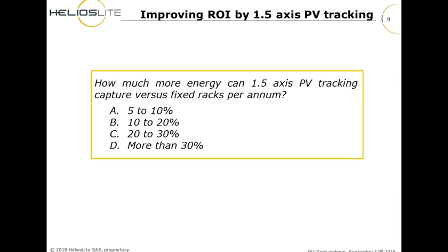That's actually a very tricky question, because it highly depends on the site latitude and the quality of the irradiance. Let me give an example of a pilot project we installed in May 2017 with Enerwhere. This system comprises 2 trackers, and we recorded an annual average energy gain of 31% versus an east-west oriented fixed system. A south-facing system at this latitude would have produced almost the same amount of energy, since we're at about 20 degrees north.